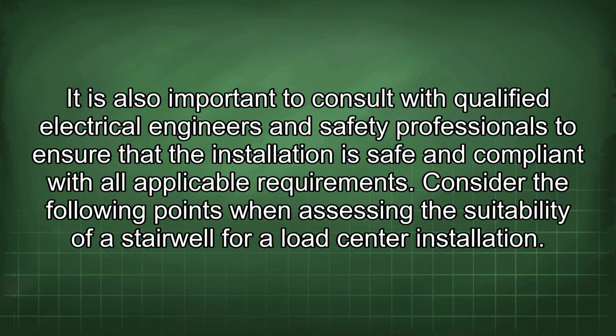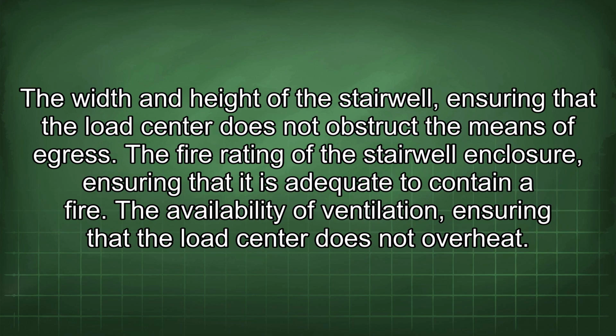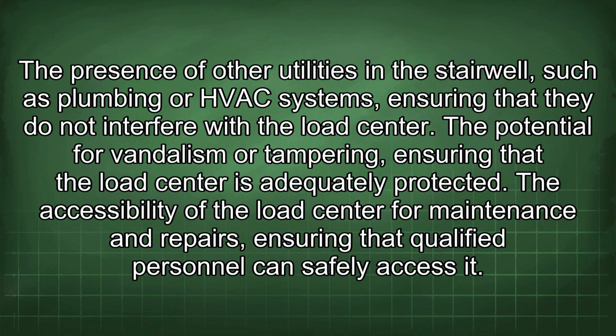Consider the following points when assessing the suitability of a stairwell for a load center installation. The width and height of the stairwell, ensuring that the load center does not obstruct the means of egress. The fire rating of the stairwell enclosure, ensuring that it is adequate to contain a fire. The availability of ventilation, ensuring that the load center does not overheat.